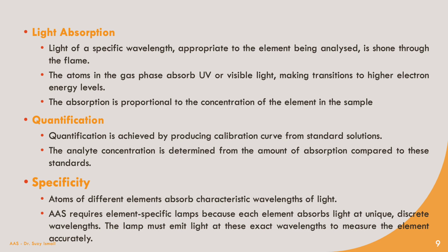So a lot of copper atoms will absorb the wavelength they love to absorb. And that will be quantified later to determine the concentration of the element. The quantification is achieved by producing the calibration curve from standard solutions. The analyte concentration is determined from the amount of absorption compared to these standards.